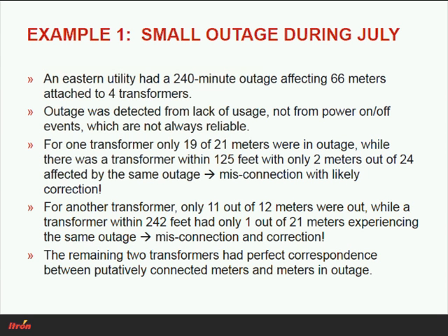All the other transformers had very good correspondence between the meters that were connected to it according to utility records. In other words, all these other transformers were either all meters were off or all meters were on during that outage period.